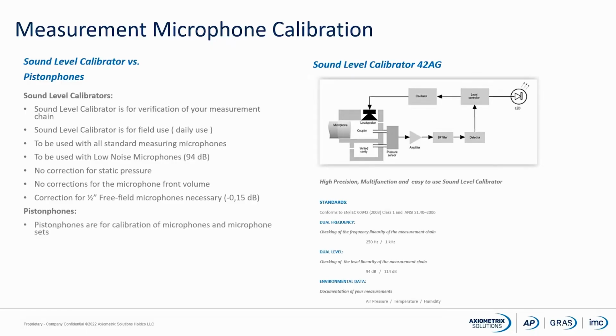If we look at the piston phone, the piston phones are for calibrations of microphones and microphone sets. It's a laboratory instrument, so it's an instrument we have to use in a laboratory. It is a very precise and accurate instrument. When it leaves the factory, we will have an uncertainty of 0.08 dB. You can also have an extra accredited calibration, and it will give you an even lower uncertainty.